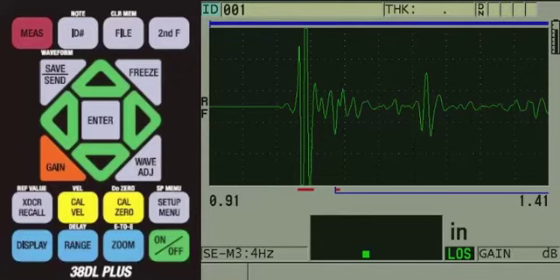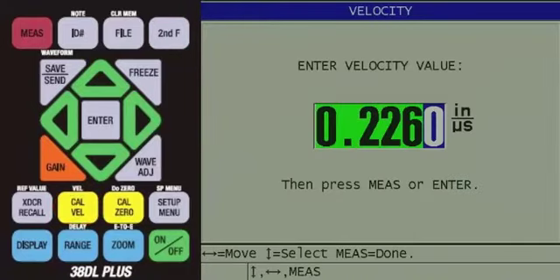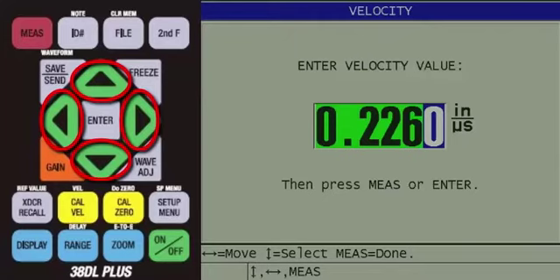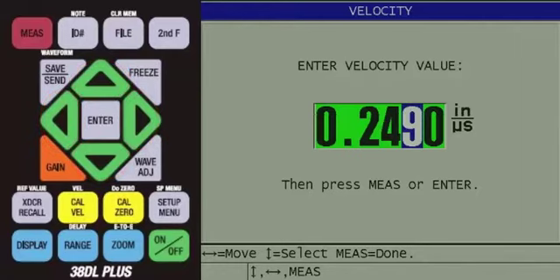To do this, press and release the second F key first, and then press the CAL-VEL key. The stainless steel velocity will be displayed. Use the arrow keys to change this value to the approximate sound velocity for aluminum, which is 0.2490 inches per microsecond, or if you are using metric units, it will be 6.325 millimeters per microsecond. Then press the red Measure key.